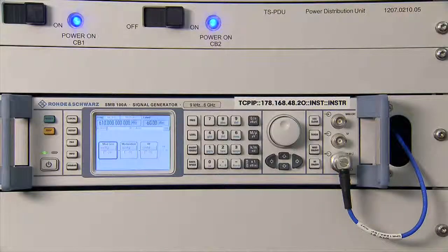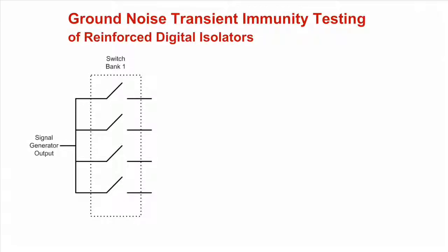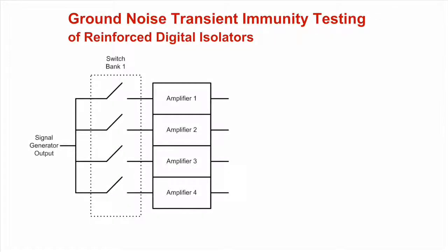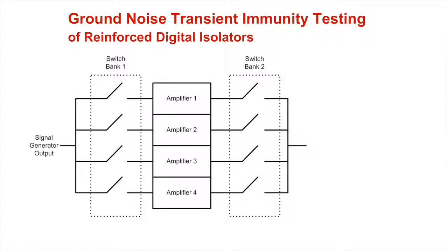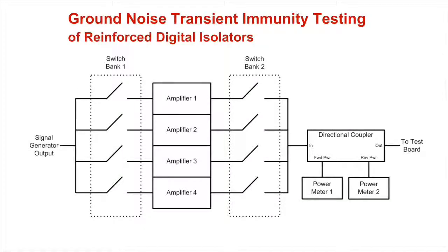Now let's look at how the GNTI signal is produced by looking at some test equipment. The first piece of equipment needed is a signal generator responsible for generating the noise source across all frequencies that you intend to test. Since this signal generator is not capable of driving the needed power levels, we have a switch bank that is used to route the noise source to a series of amplifiers that are each only capable of properly amplifying the noise signal for a subset of the full frequency range. At the output of the amplifier is another switch bank that routes the output signal to the coupling network. This coupling network has a pass-through port routed to the test board and two additional ports used for power meters to measure the forward power and reflected power in the test setup real-time. This closes the control loop and allows you to monitor and ensure that the desired power is always being applied at each amplitude step.